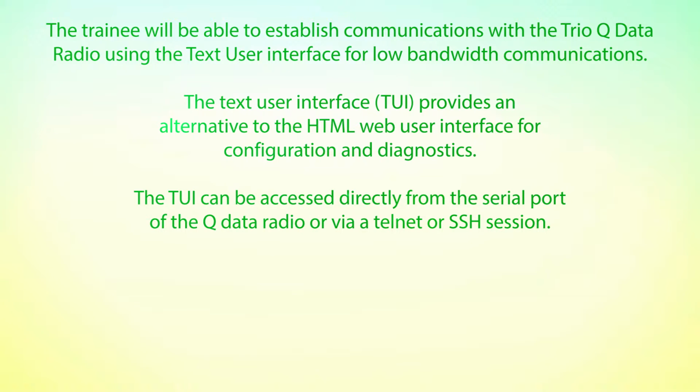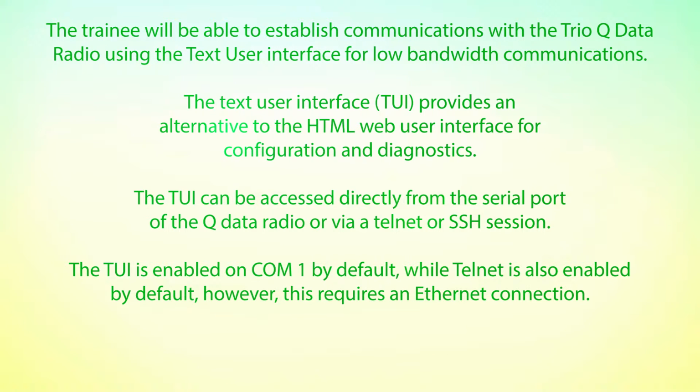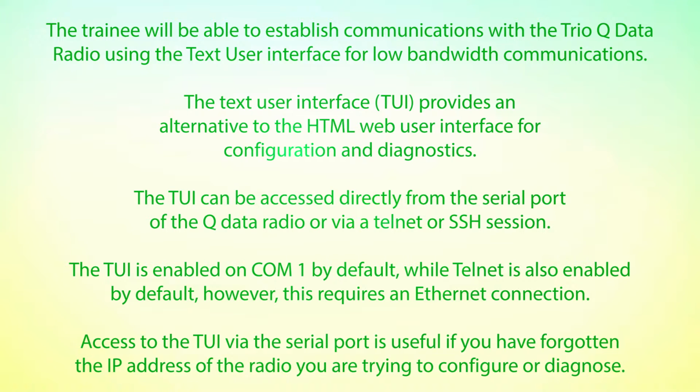The TUI can be accessed directly from the serial port of the Q data radio or via a Telnet or SSH session. The TUI is enabled on COM1 by default, while Telnet is also enabled by default. However, this requires an Ethernet connection. Access to the TUI via the serial port is useful if you have forgotten the IP address of the radio you are trying to configure or diagnose.